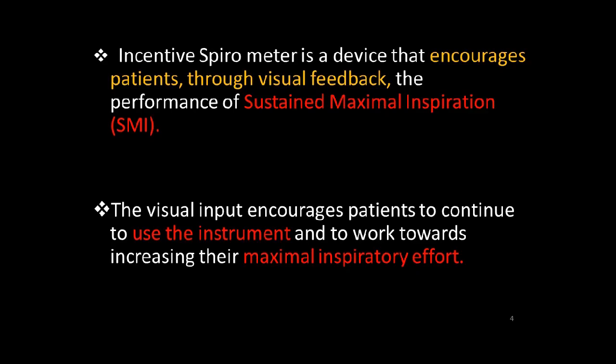The incentive spirometer is a device that encourages patients through visual feedback — that means the patient can see how they are performing the SMI, which stands for Sustained Maximal Inspiration. This visual input or biofeedback encourages the patient to use the instrument and work towards increasing their maximum inspiratory effort.